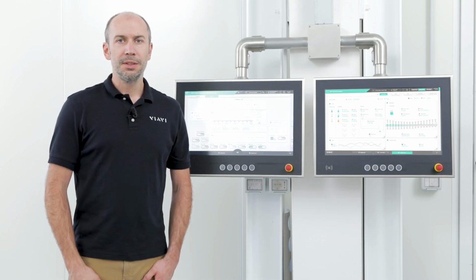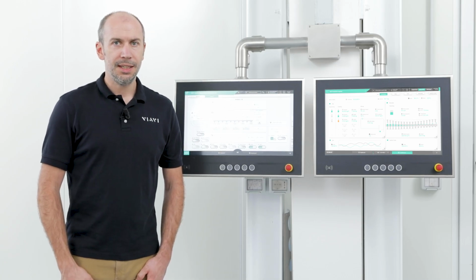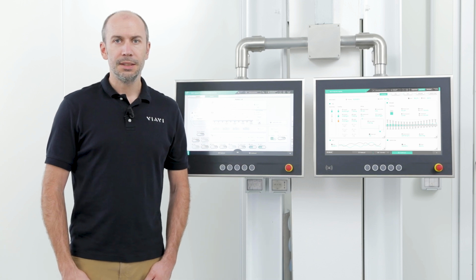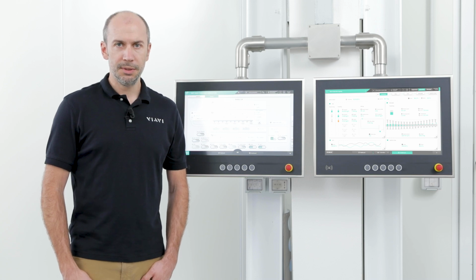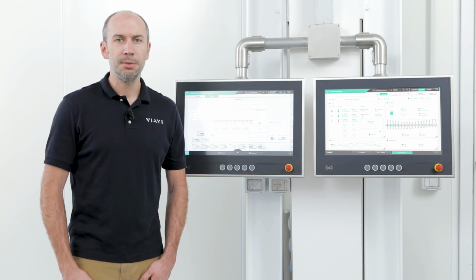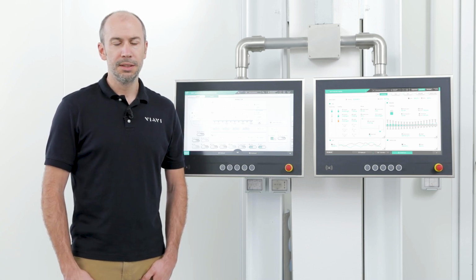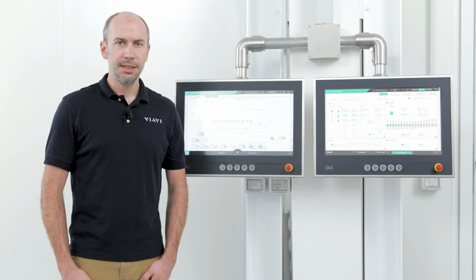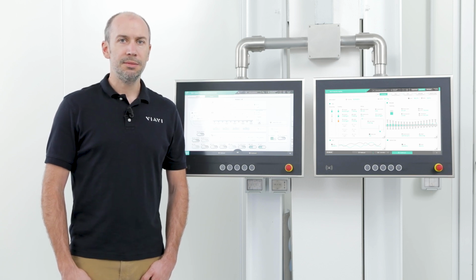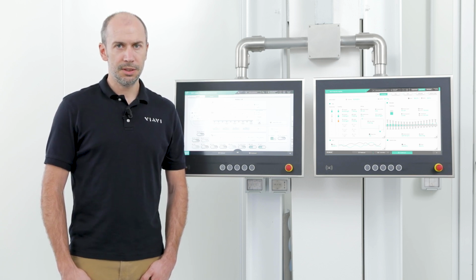Finally, an overlooked advantage of the LVF is high light transmission. This allows high signal-to-noise ratio with a reduced requirement for sample illumination. This allows the lamps to be run below their rated power, greatly increasing their life. In fact, in 10 years, we have not had a single instrument returned to us due to lamp wear.